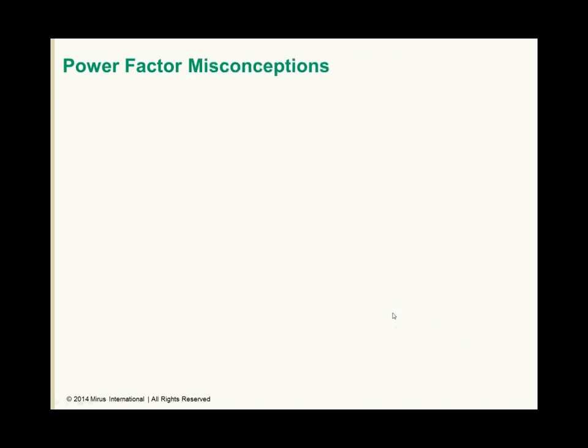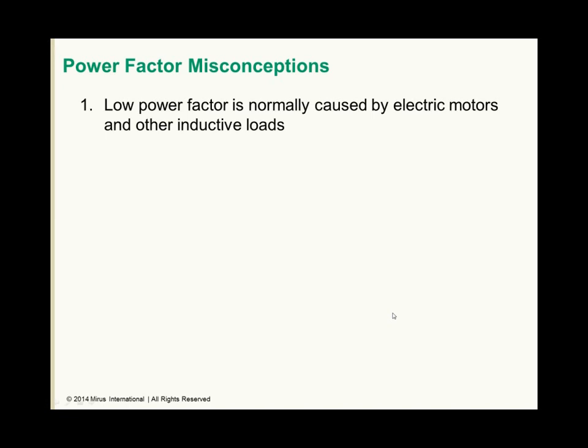The 6 misconceptions of power factor, with the first being that low power factor is normally caused by electric motors and other inductive loads. Although it is true that inductive loads consume reactive power and thereby reduce power factor, with today's proliferation of harmonic generating power electronic nonlinear loads, low power factor is now most often caused by harmonics.